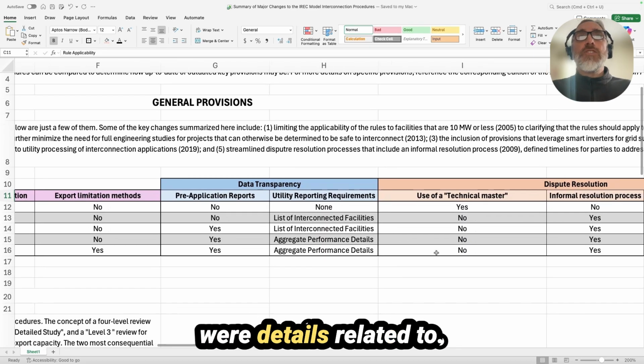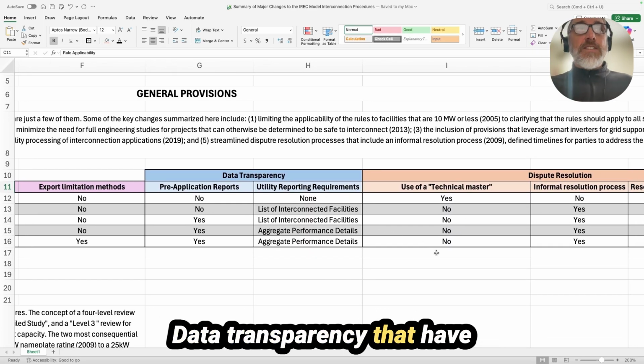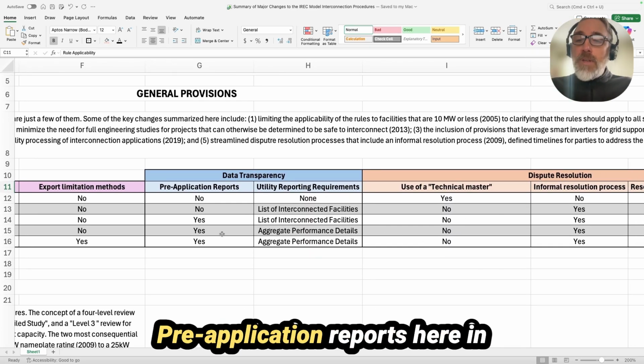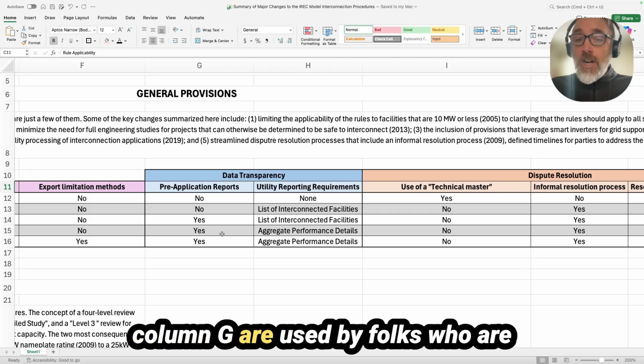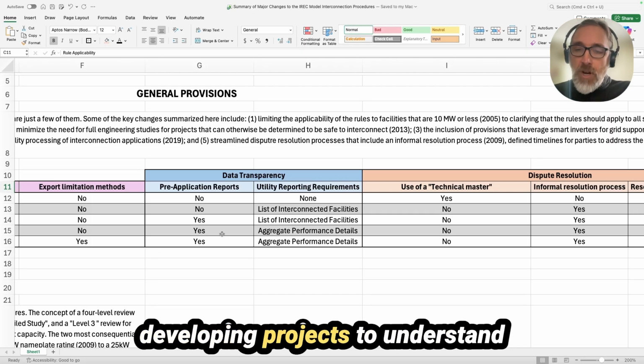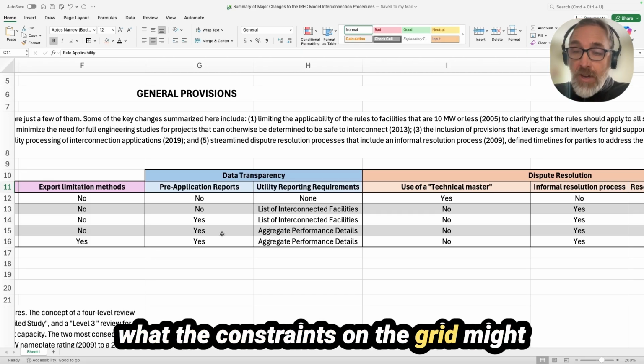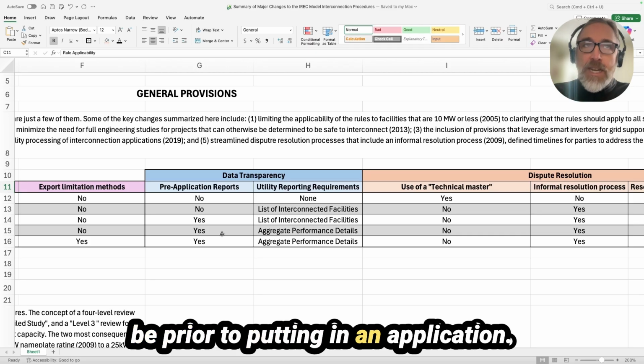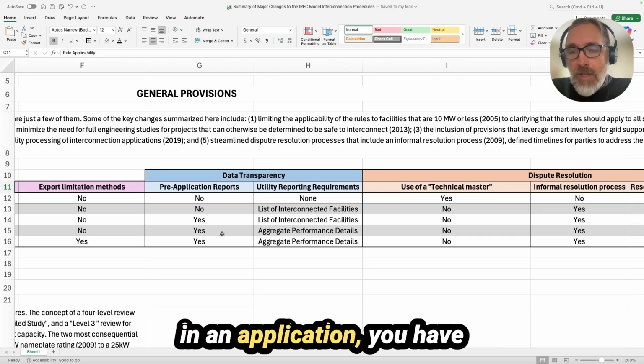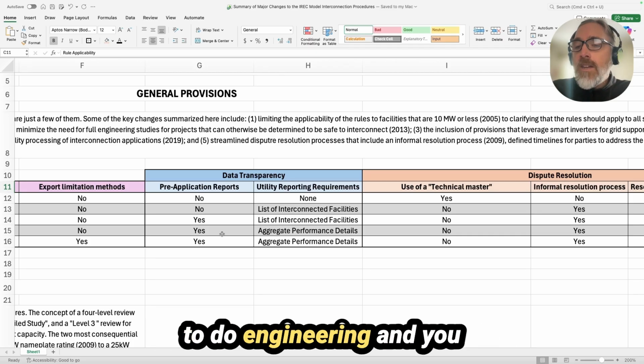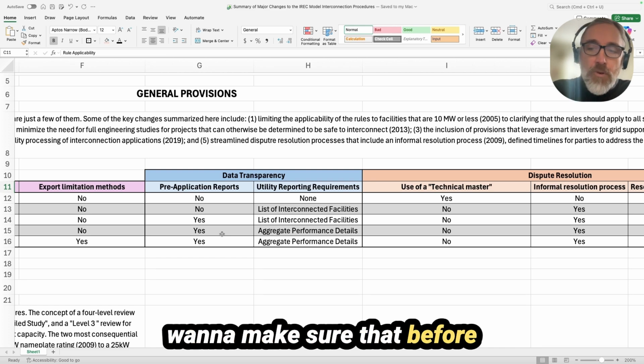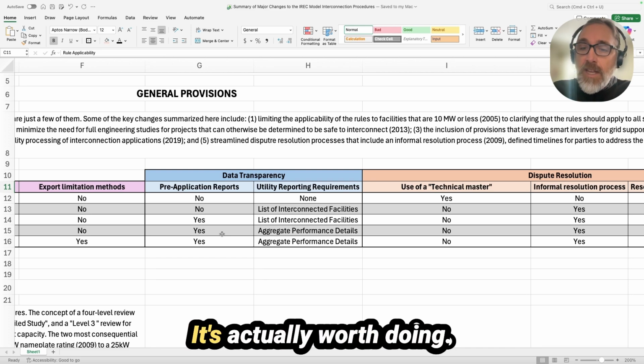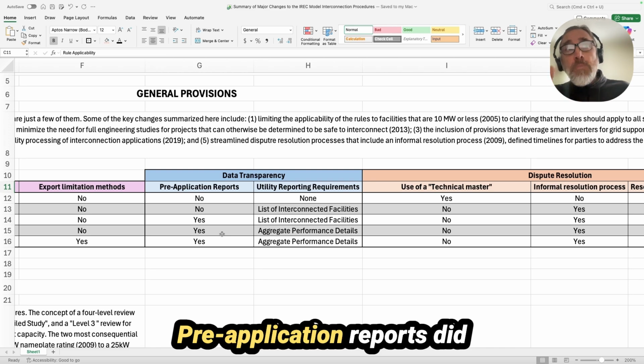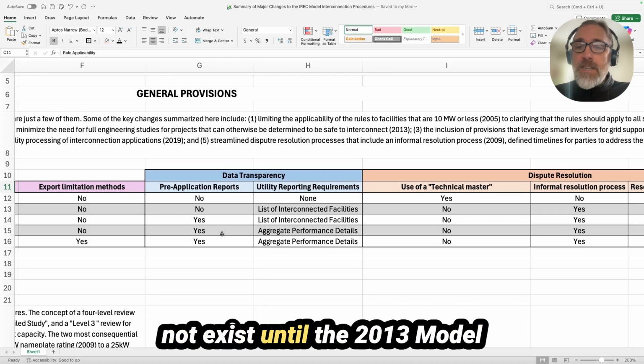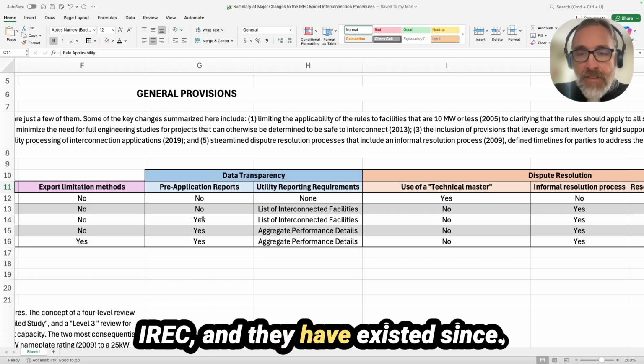Additionally, there were details related to data transparency that have changed over the years. Pre-application reports here in column G are used by folks who are developing projects to understand what the constraints on the grid might be prior to putting in an application. There's a bunch of costs in putting in an application. You have to do engineering, and you want to make sure that before you go through that process, it's actually worth doing. Pre-application reports did not exist until the 2013 Model Interconnection Procedures from IREC, and they have existed since.